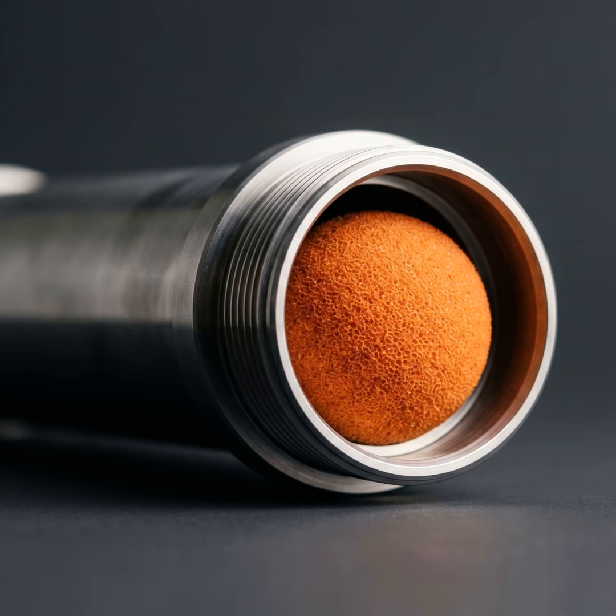A huge problem. As that crucial heat transfer occurs, as the temperature fluctuates across the surface of the copper, those dissolved minerals literally precipitate out of the water. We were primarily talking about calcium carbonate and magnesium. Yeah. And due to the unique chemistry of calcium carbonate, it actually becomes less soluble as it gets hotter. Really? Yeah. Most things dissolve better in hot water, like sugar in tea. But calcium carbonate is the opposite. Oh, wow. So right at the hottest point, the surface of the condenser tube, the minerals just drop out of the fluid. Exactly. And they don't just float away harmlessly. They do not. They cling to the internal walls of those pristine copper and titanium tubes.